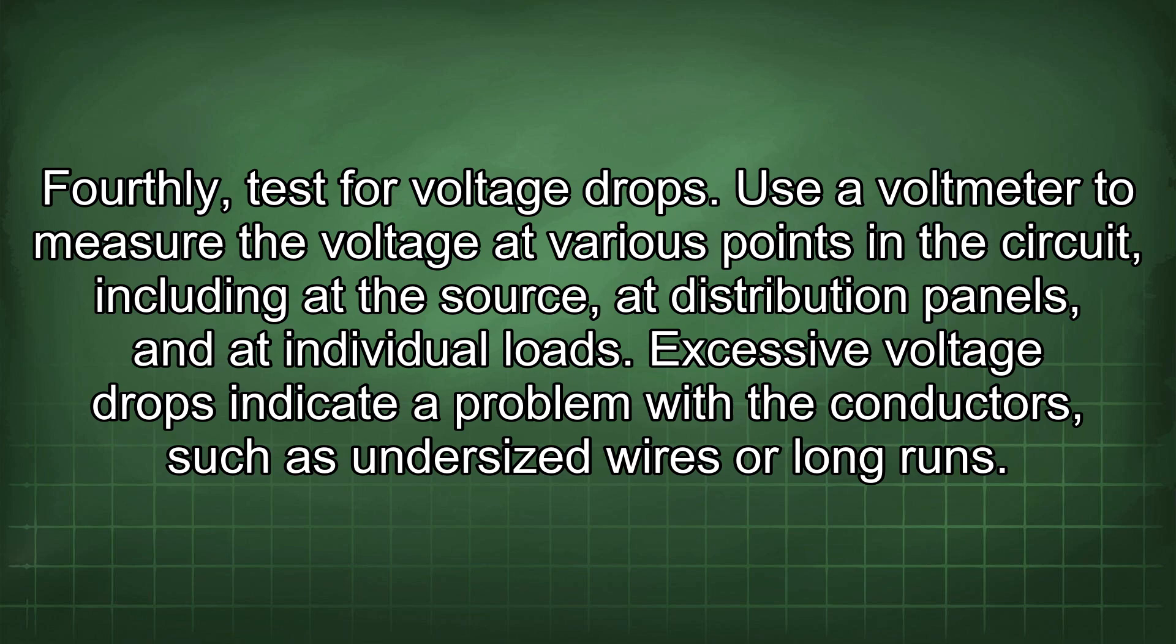Fourth, test for voltage drops. Use a voltmeter to measure the voltage at various points in the circuit, including at the source, at distribution panels, and at individual loads. Excessive voltage drops indicate a problem with the conductors, such as undersized wires or long runs.